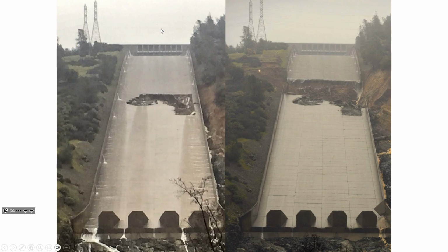But there was an issue. There was a concrete fault where, even with the smallest defect, water's going to find a way to get in there. It's going to begin scouring material out. Cavitation can occur when velocities are really high. And that's where there's a small shock wave that's being sent through the water due to negative pressures, and it chips away at the concrete. And the hole progressively got worse.